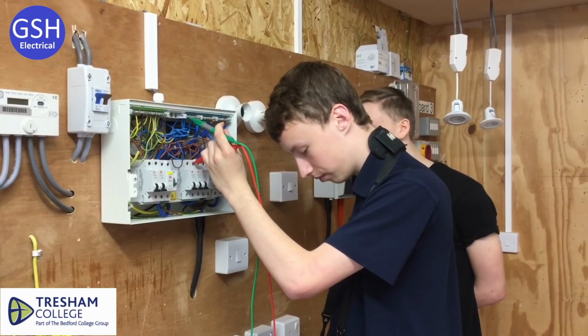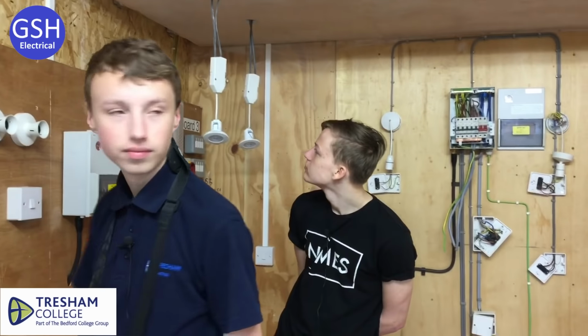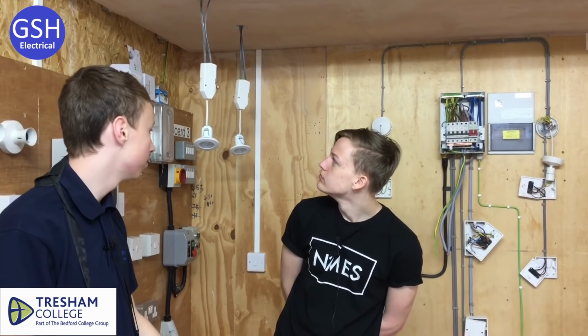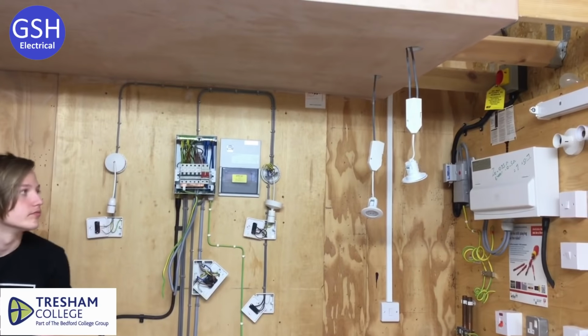As we're passing 500 volts through the circuit, Harrison, and those light fittings are hanging down, have we passed 500 volts through each of those LED light fittings? No. What have we done to the fittings themselves? We've taken the line out of them. Okay, we've taken out a line for each of those, so we're going to need to put those back in when we go live.